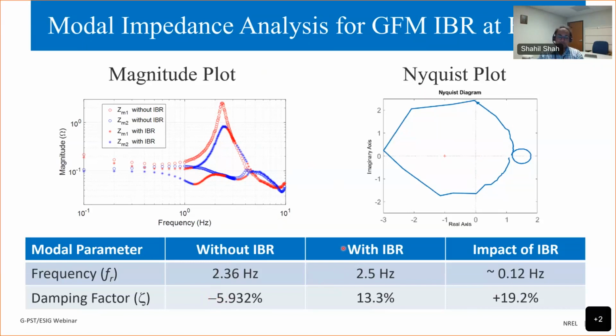Because we started with the premise that with the IBR the integrated system is stable, we want to understand if we remove the IBR, whether the system remains stable or becomes unstable. During this analysis, we find that this particular grid forming inverter plant at bus 6 increases the oscillation mode frequency from 2.36 hertz to 2.5 hertz. And it improves the damping from minus 5.9% to 13%, or basically by 19%. So this is the impact of this particular IBR. This also shows that if we remove or curtail this IBR, the damping will become negative, and this mode will actually become unstable.